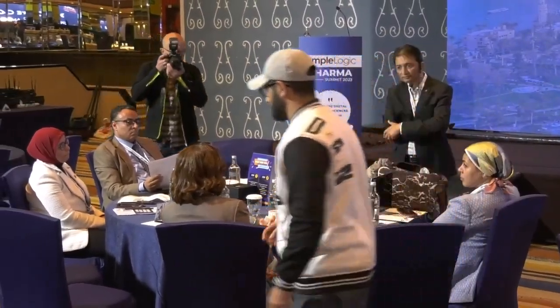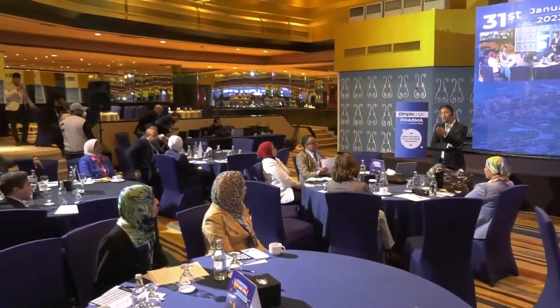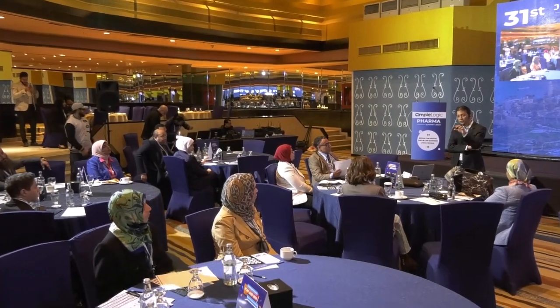You have to challenge minimum and maximum also. I cannot rely on one point unless I make a validation for this verification and I assure that the minimum checkpoint, using one balance unit, will cover all the risk in my working range. Let me address her first. Give the mic.